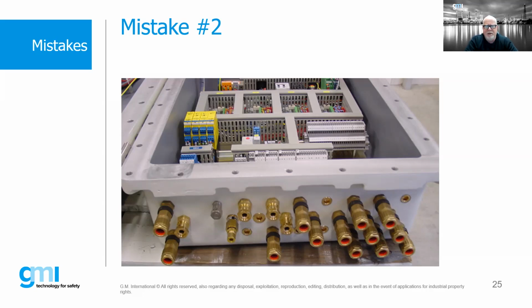So in this particular instance, at first glance, we may say this is perfect, but then all of a sudden we start looking at the drawing and there might be additional components that were put in, or maybe there was additional entries that were drilled and tapped. And even though they look fine, if it wasn't done by either the manufacturer or a service center, those could be potential issues based upon the fact that it may be too close and we could potentially rupture the enclosure, in this case, an EXD box. So even if everything looks fine, we still want to check it out and compare it versus what should have been produced.